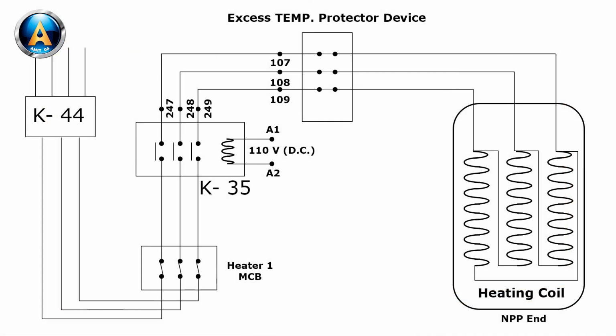415 volt 3-phase power reaches the heater unit at the non-power plant end through K44 contactor, heater 1 MCB, K35 contactor, panel terminal, roof terminal, and excess temperature protector device.